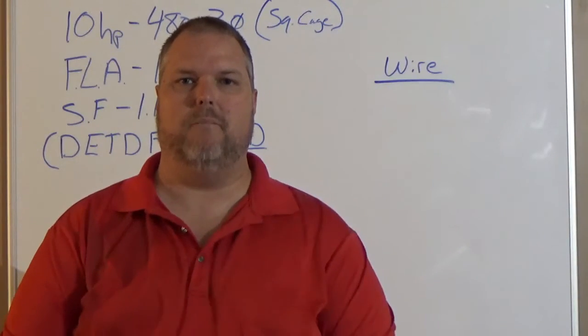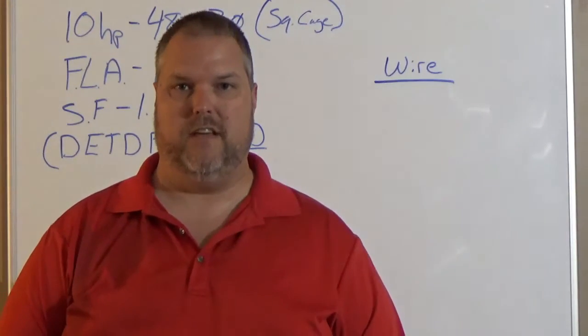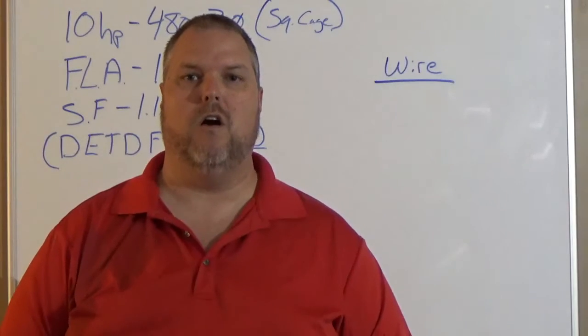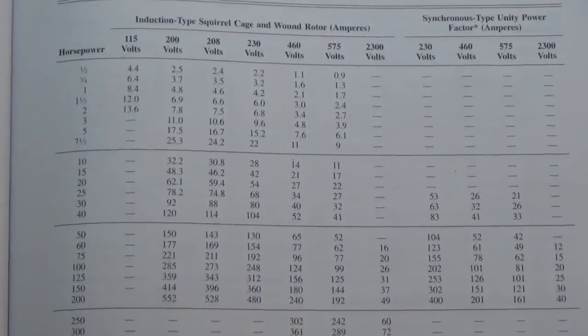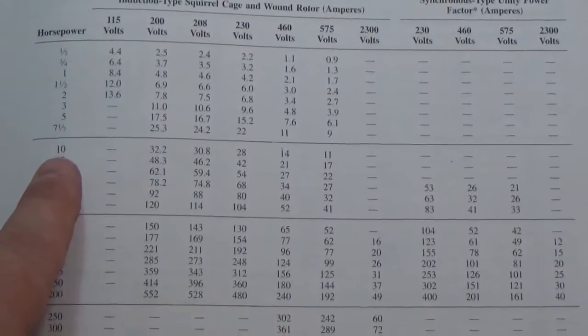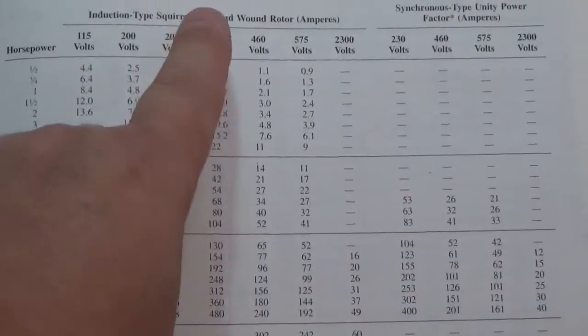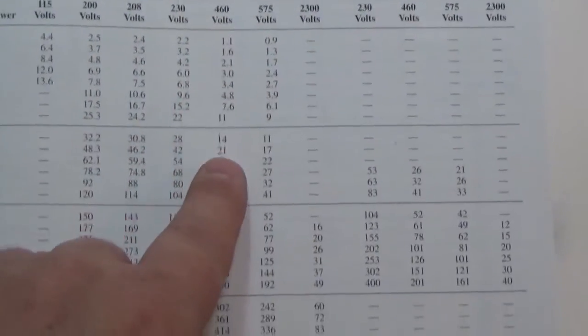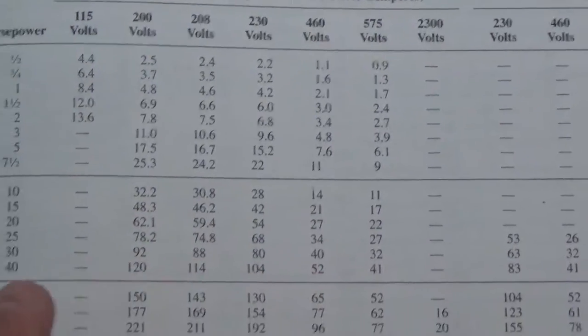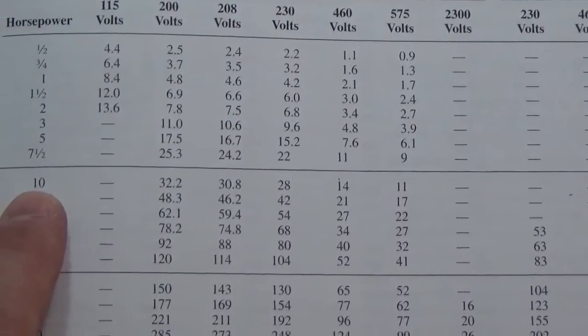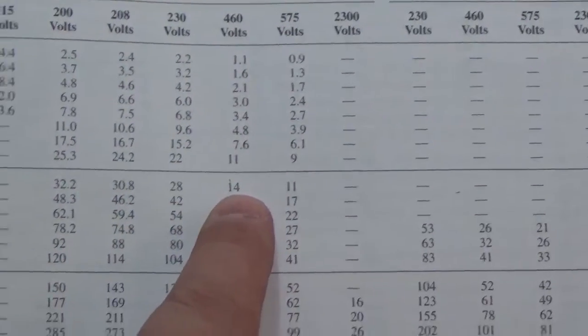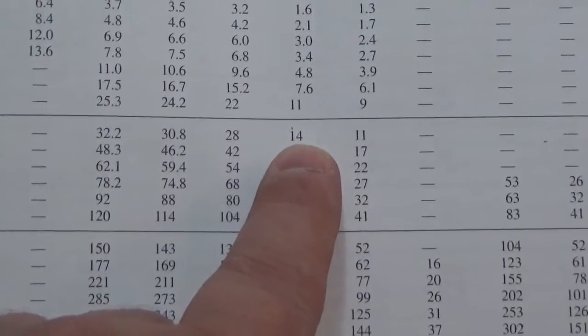The thing we need to do is we need to find the FLC. So what does that mean? We need to go into 430.250. And we're going to figure out what our FLC is for a 10 horsepower, 480 volt, three-phase motor. So we're at a 10 horsepower. We have 480 here. We use the 460 chart and I'll explain that in a minute. We go down and we find 10 horsepower top line. It is 14 amps.